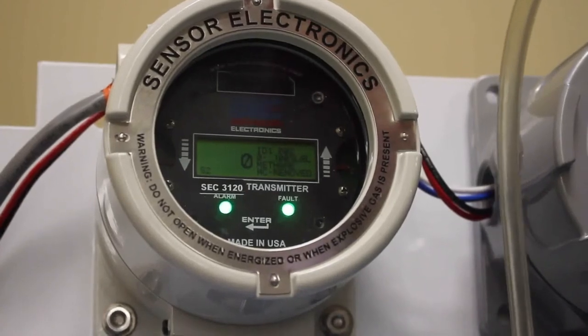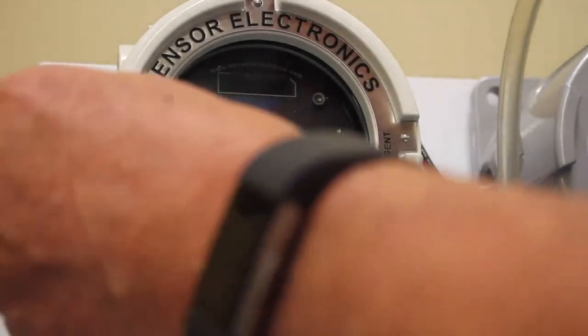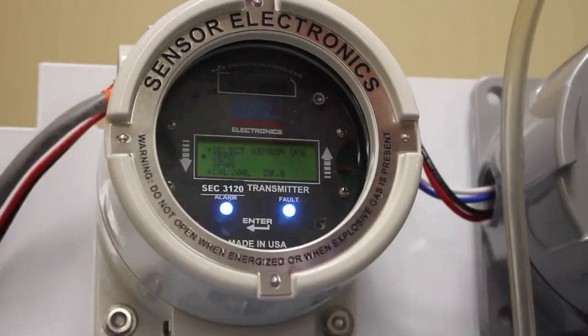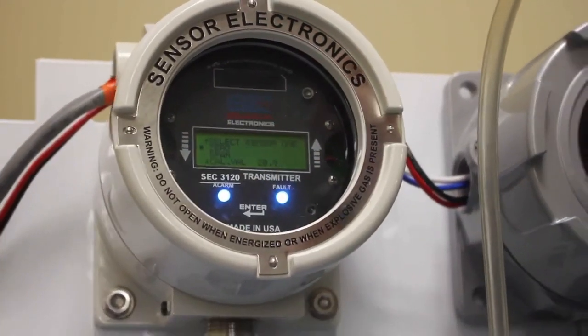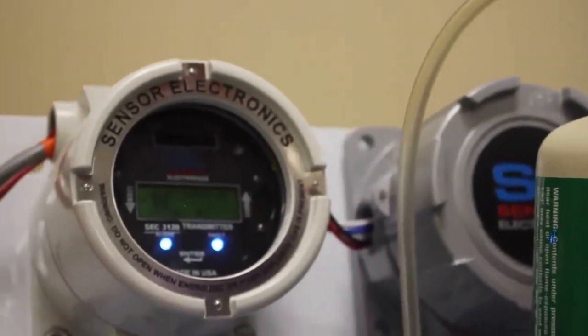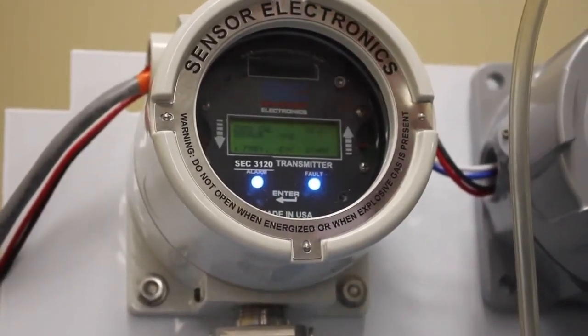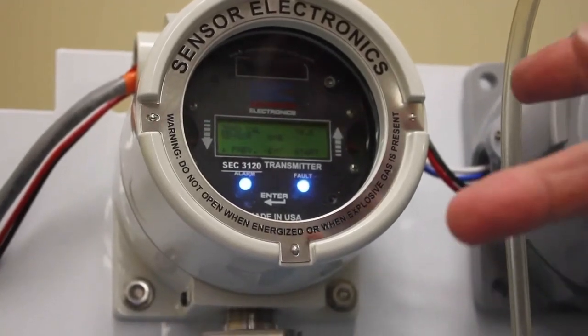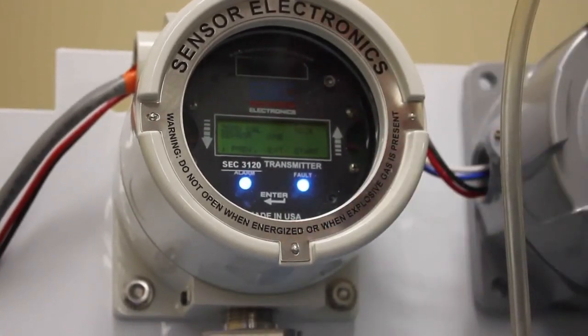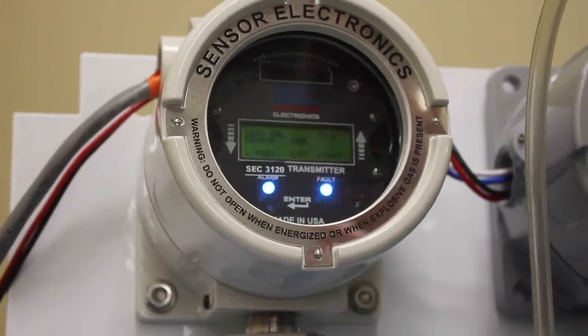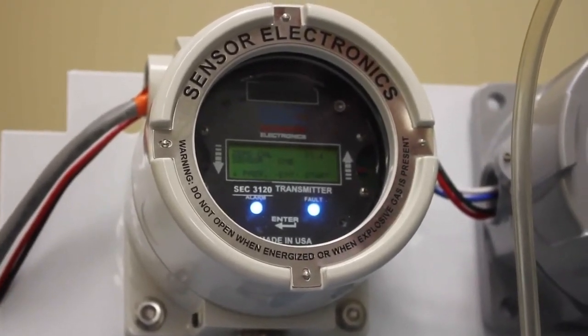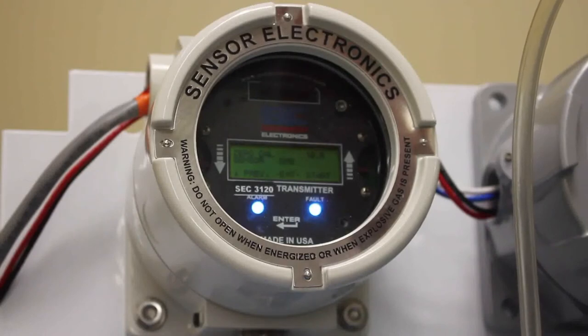And to zero the oxygen sensor, I guess it must have timed out. Zero, what we'll do is we'll open up the cal gas cylinder. And then we can actually see the reading of the sensor once we selected the zero, and you'll see that applying nitrogen to the oxygen sensor is going to drive the signal down. And you'll always want to zero the oxygen sensor in nitrogen, because normally it's going to be sensing oxygen presence. So we can use the ambient air to actually span the oxygen sensor or a different calibration gas cylinder.